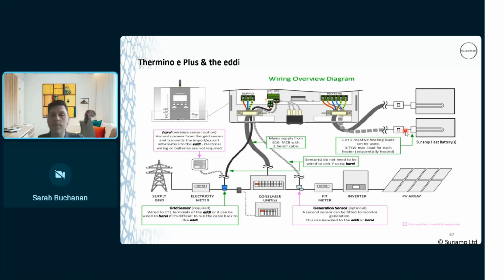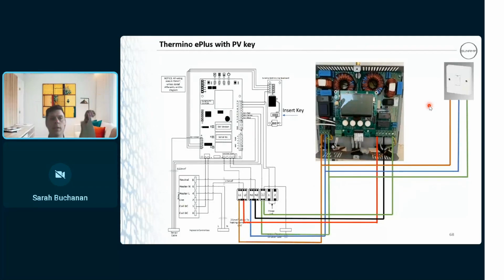Plumbing wise, you'd have to fit them in series, not parallel. So your primary unit would be your outlet battery. Your secondary unit would be your inlet battery when it comes to the plumbing. So your cold mains would enter your secondary battery first, and then your hot outlet would be your primary battery, if that makes sense. All right, so it just shows you what can be done. And that's pretty much how you wire it up.